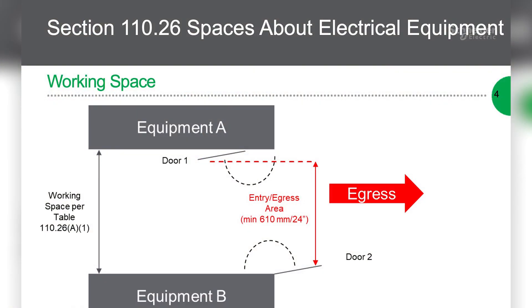My biggest concern is with multiple equipment lineups — pieces of equipment that face each other where opening doors could intrude into each other. When we think about multiple equipment lineups, there are so many additional configurations to consider. In the graphic with facing lineups, you have to account for open doors in both lineups and verify you still maintain the 24-inch egress entrance path.